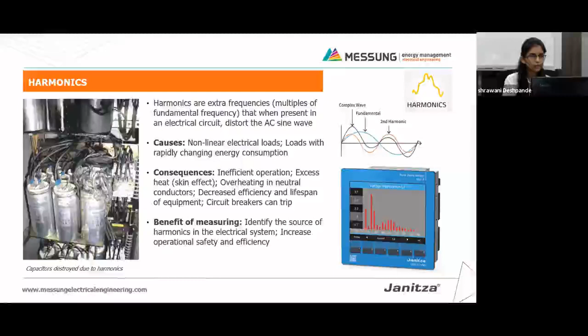Then another aspect regarding harmonics is that your loads, that is non-linear loads, will generate current harmonics, and these will be put back into your own facility and then to the utility grids. And there, they will cause the distortion in the waveform, that is voltage harmonics. So if in your facility you are generating harmonics, then you will end up in a situation where you will have to pay for it because utility companies will charge for having this poor power quality. Now, you must be thinking, how would I know whether my facility is generating harmonics or not, or whether I am complying to IEEE 519 standard limits or not. So the answer for this would be continuous monitoring. By monitoring your facility continuously, you would be able to identify the sources of harmonics within your facility.